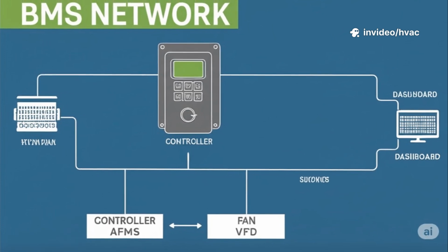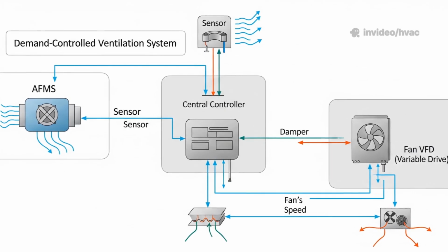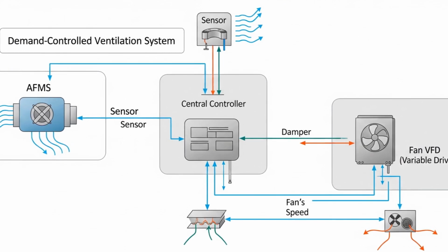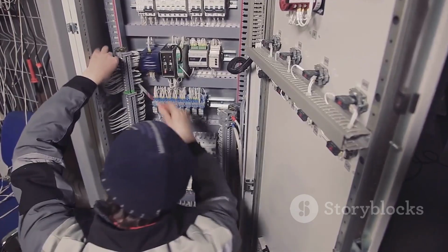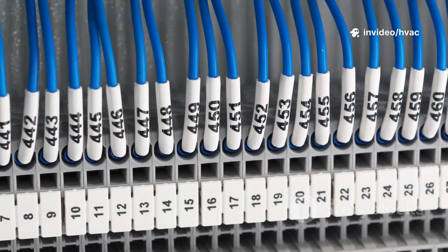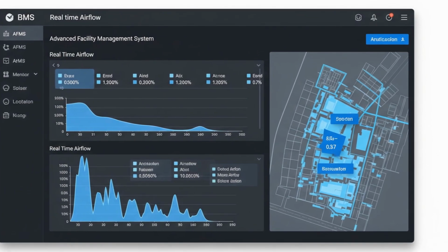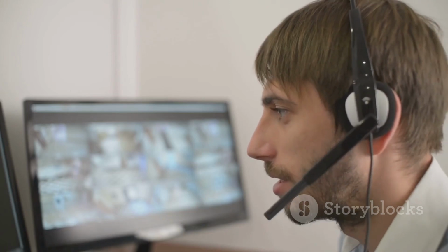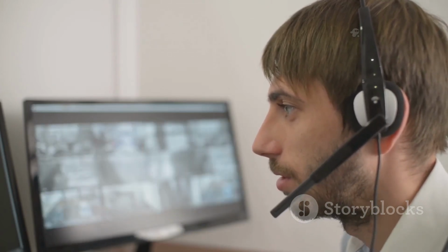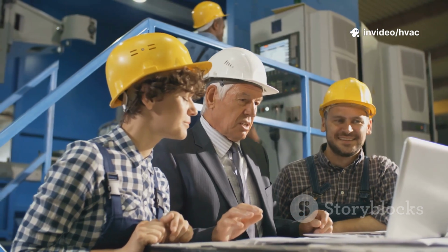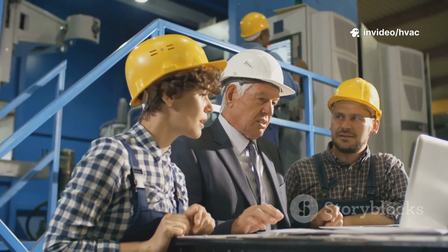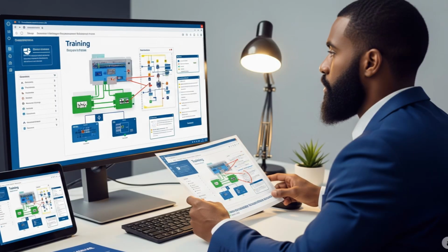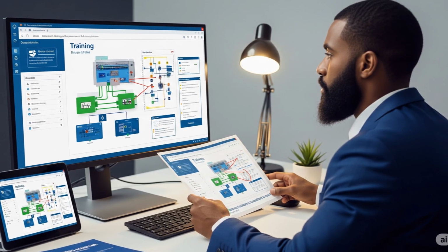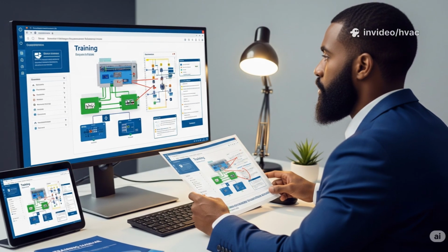Modern airflow measuring stations are deeply integrated with building management systems. Accurate flow data enables demand-controlled ventilation, dynamic fan speed control, and even fault detection. Make sure your signal wiring is correct, whether it's analog like 4 to 20 mA or digital such as BACnet or Modbus. And always validate that your BMS trends actually match the real site conditions. Regularly review BMS alarms and alerts to quickly identify and resolve any discrepancies or system faults. Schedule periodic maintenance and software updates to ensure your BMS and airflow measuring stations operate at peak performance. And don't forget to train your staff on BMS operation and troubleshooting so they can respond effectively to any issues that arise.